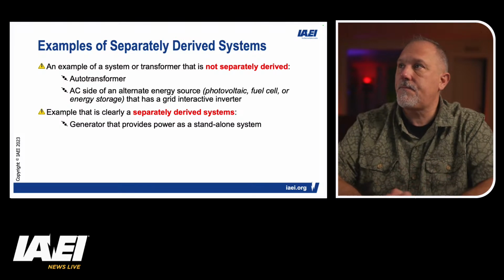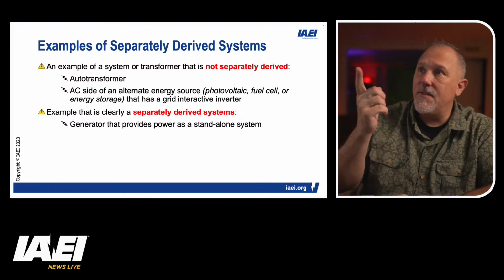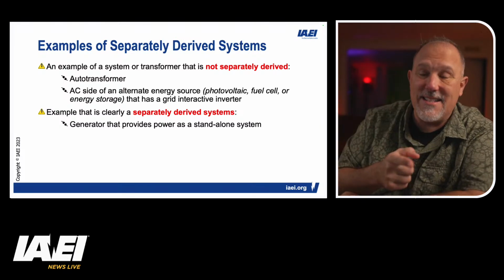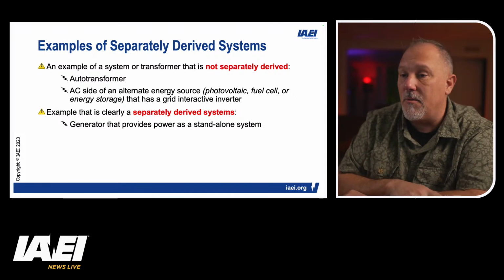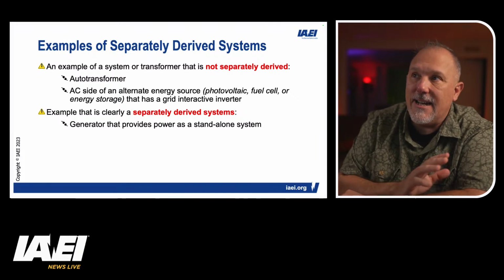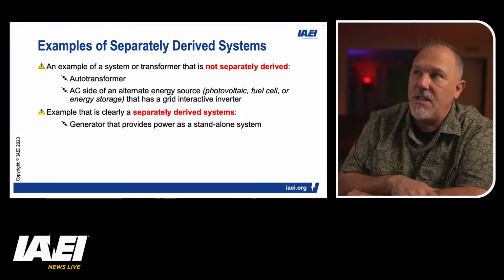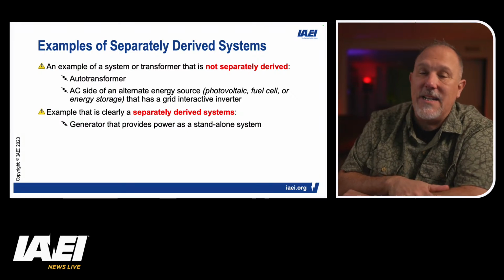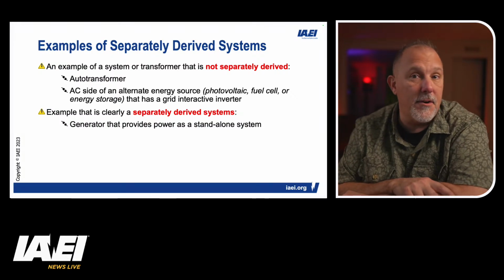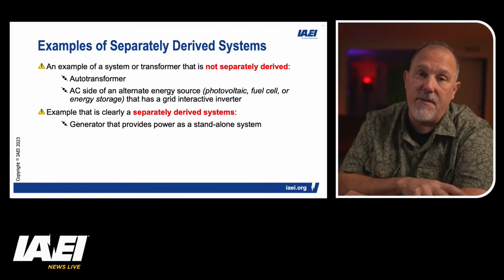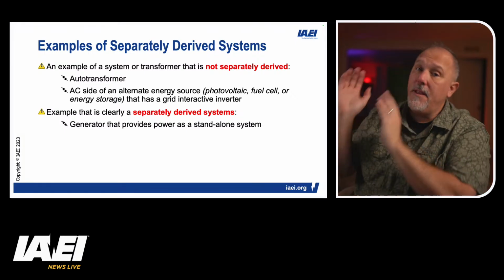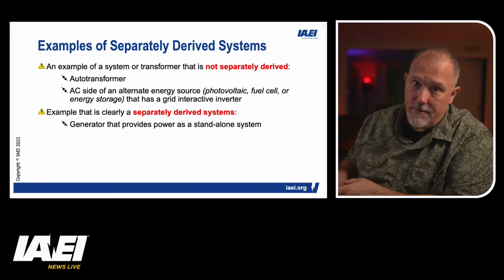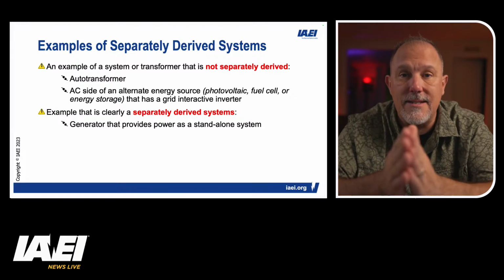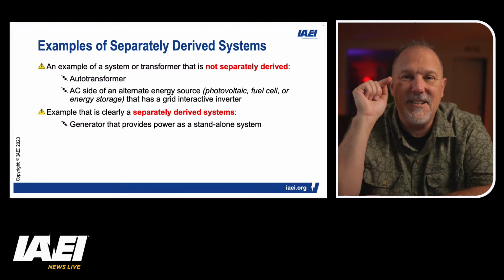Make sense? An example of a system or transformer that is not separately derived: there's the autotransformer example. Another is the AC side of an alternate energy source that has a grid interactive inverter. When we say grid interactive inverter, when the grid shuts down, the inverter shuts down. It's going to be listed as such. Again, it's a defined term.